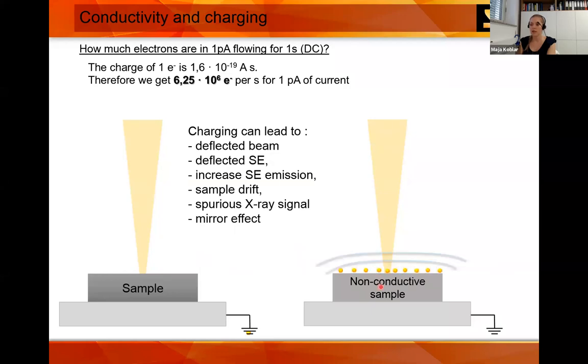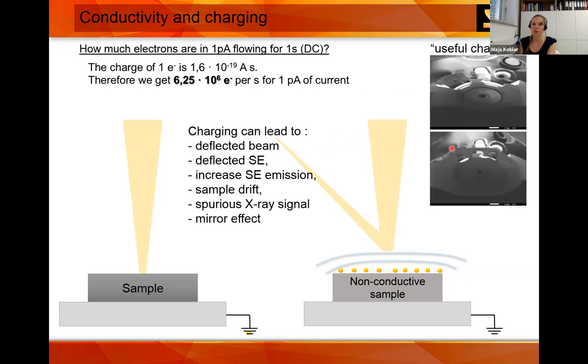When you have many electrons, they produce an electric field. If you lower the energy of your primary beam, it scans the top of your chamber instead — you can actually see the chamber interior: the pole piece, VDS detector, EDS detector, secondary electron detector, EBSD port, and retractable backscattered detector. Note that if you have charging, the scale bar and magnification definition are not correct, so you must be aware of this.